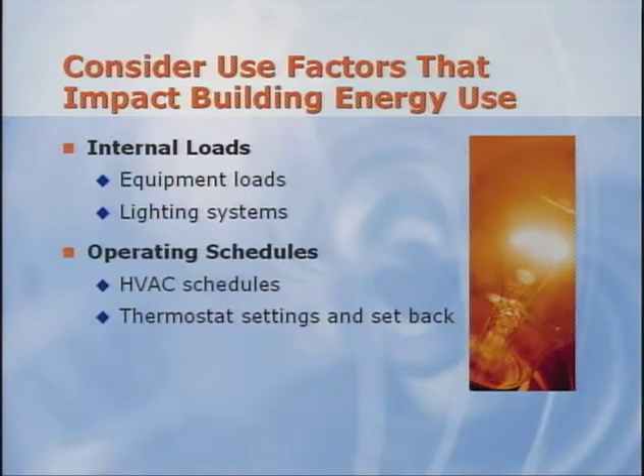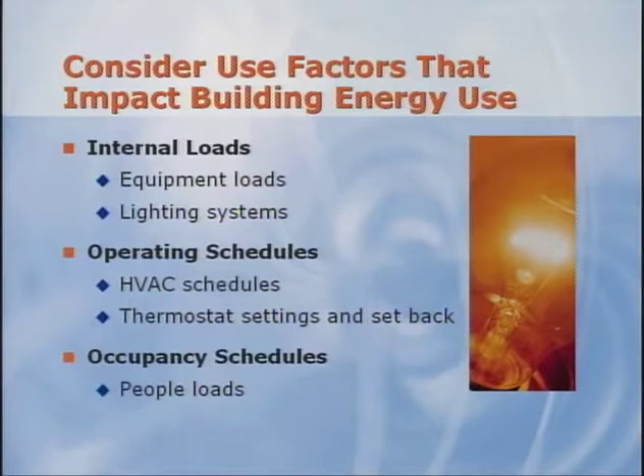Often we find building systems operating to maintain temperature or provide ventilation for areas of the building that are long since unoccupied. Often, this is because the outdated original design criteria no longer exists. Beyond proper scheduling, having an HVAC system that can automatically respond to the varied occupancy can have a huge impact on the energy bill. The impact of energy consumed by office equipment has grown substantially over the last few decades and can be a significant amount of the energy use in a building today.